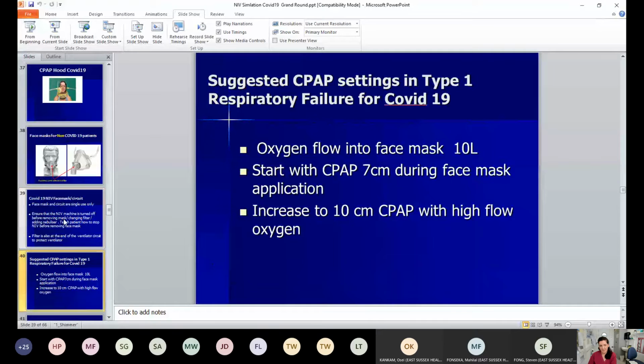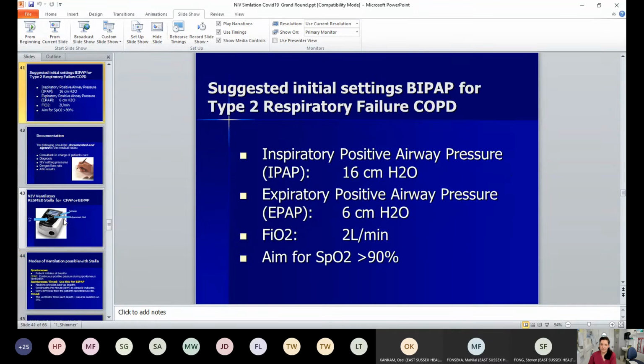The other filters that we use are at the end of the ventilator circuit to protect the machine, and they're single use only. We'll be running the CPAP at 10 litres of oxygen with a pressure of 7, and we'll increase it to 10 and then 15. And if the patient's in type 2 respiratory failure, we'll be using BiPAP with a starting pressure of 16 centimetres of water and EPAP of 6. We're aiming for SATs of 90%.